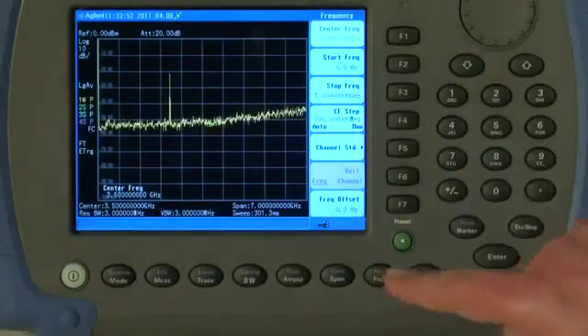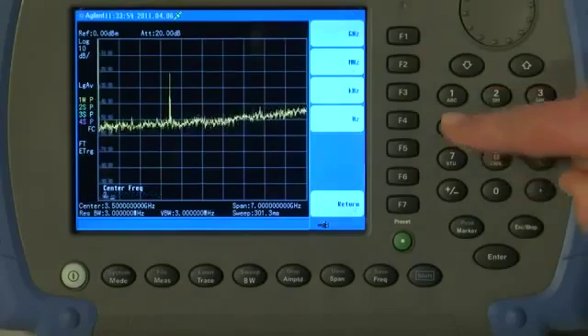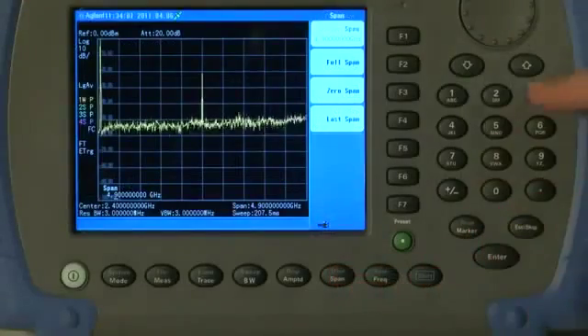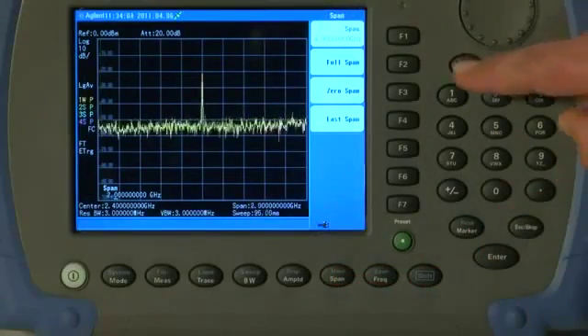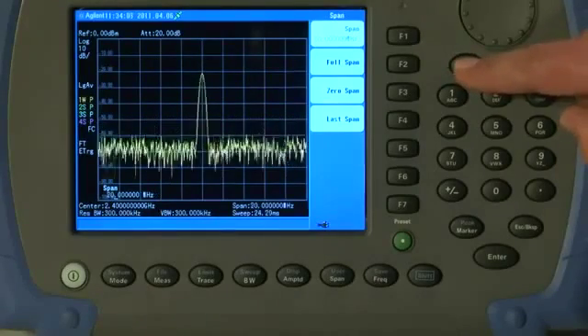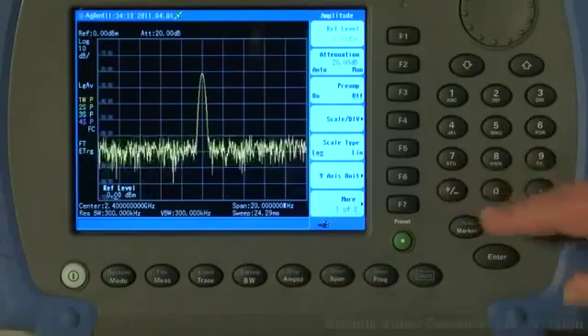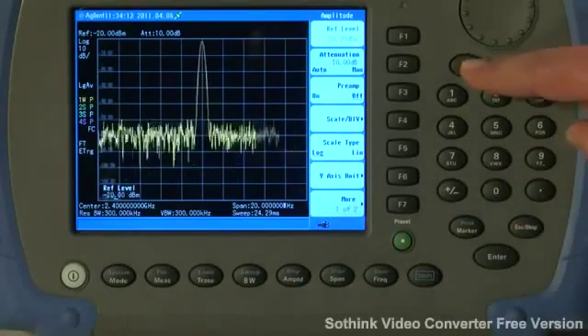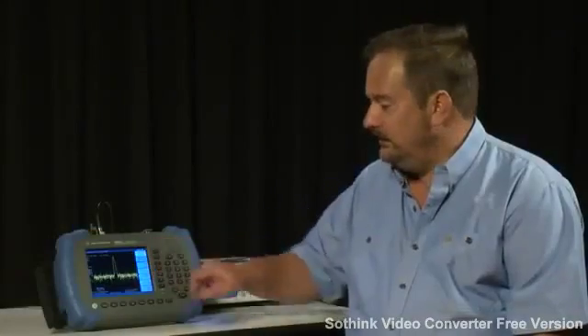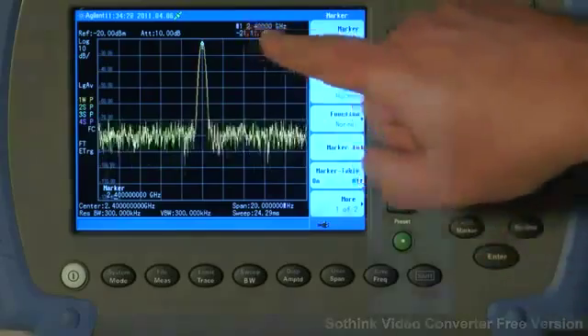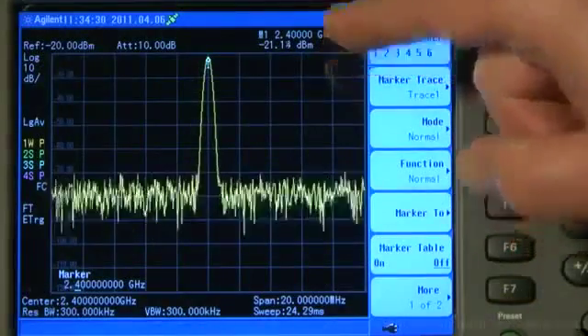If we know what frequency the signal is, we can simply press Frequency and enter, in this case, 2.4GHz. That tunes the signal to the center of the screen. I can then press the Span button and using the down arrow keys, I can zoom in on the signal. I can press the Amplitude button and change the reference level, again using the arrow keys to bring the signal to the top of the Graticule, and then I can press the Marker button and read the amplitude value of the signal, approximately minus 20 dBm.